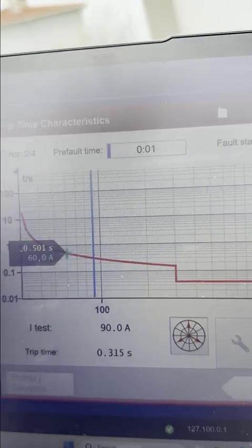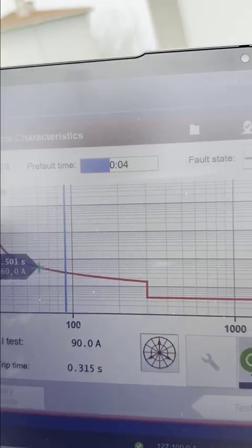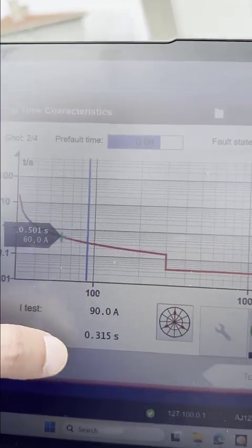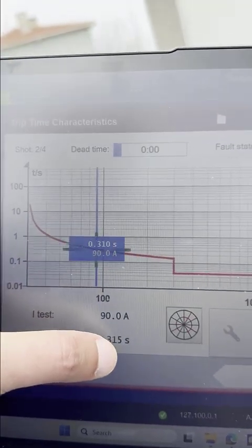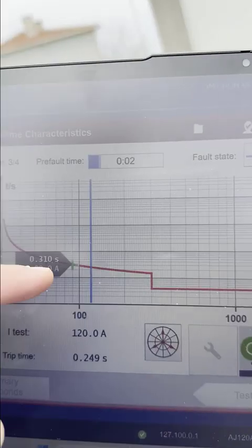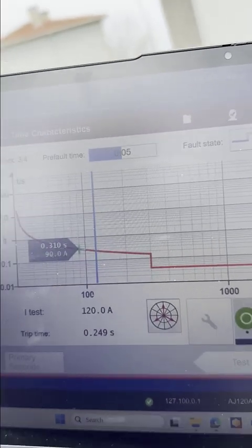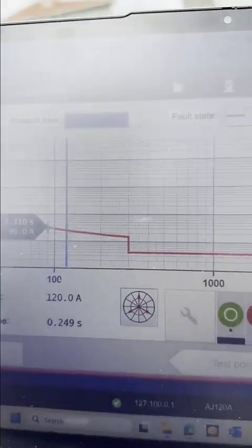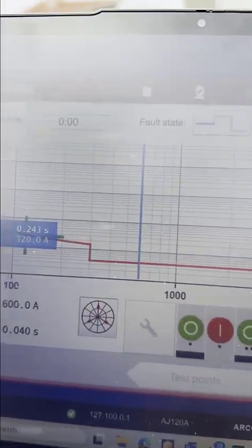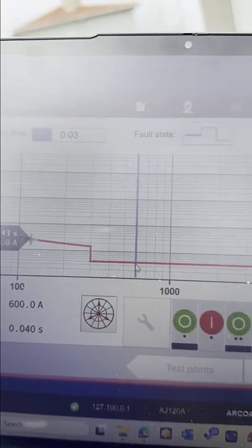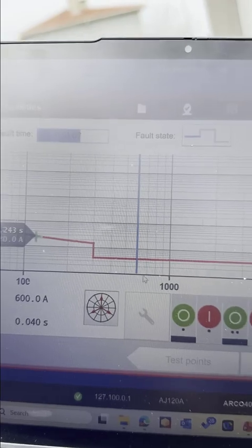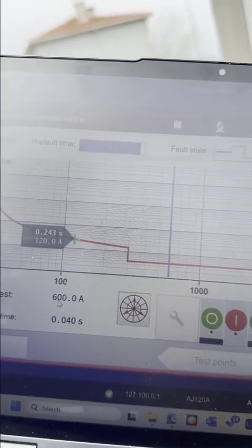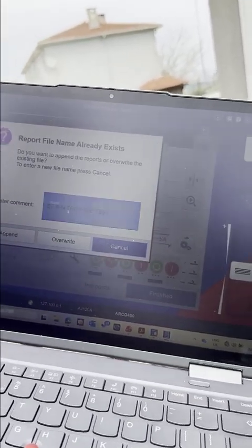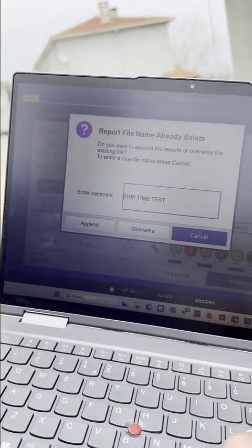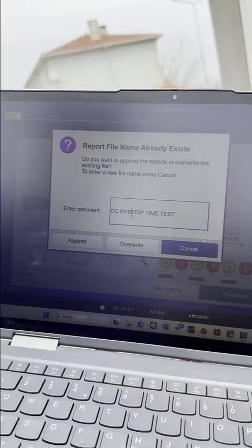Okay, so 501. Now it's pre-fault and the circuit breaker closed again before the second shot at 90 amp, and the expected trip time based on the IEC normal inverse equation is 315 milliseconds. Now it's 310 millisecond and it's assessed as pass. If you see this green plus, means the test is automatically passed or automatically assessed as passed based on the tolerance. Here is the third one, 243, and here now this is a pre-fault stage before the last shot, which is a definite time shot, and the expected is 40 milliseconds at 600 amp, which is now 59 milliseconds. Then you can save this result as we did with the ARCO 400 to be overcurrent RYB trip time test.